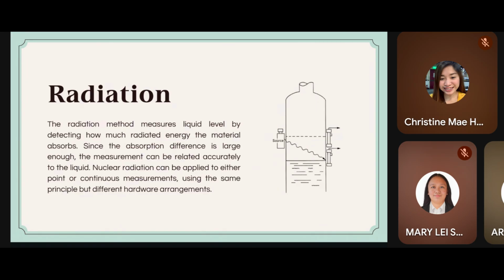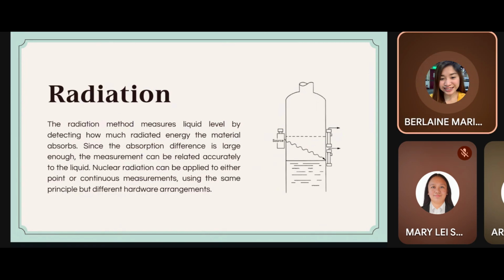Next naman po ay ang radiation. So basically, in this method, the material inside the tank absorbs some of the radiation that passes through it. The amount absorbed depends on how much material is present, which makes it possible to determine the level. Ang maganda po dito is that it works whether we just want a specific level check like at one point, or kaya naman a full continuous measurement. The principle is always the same, but the setup of the equipment changes depending on the application. Next slide, please.